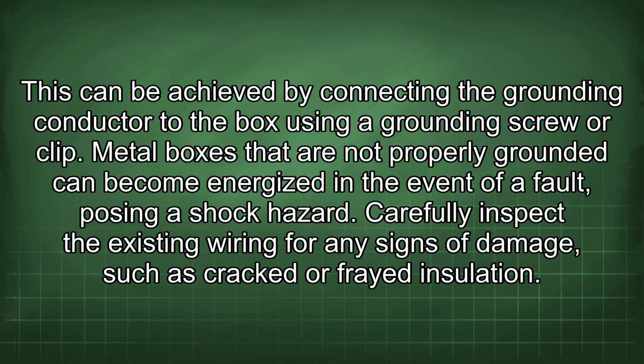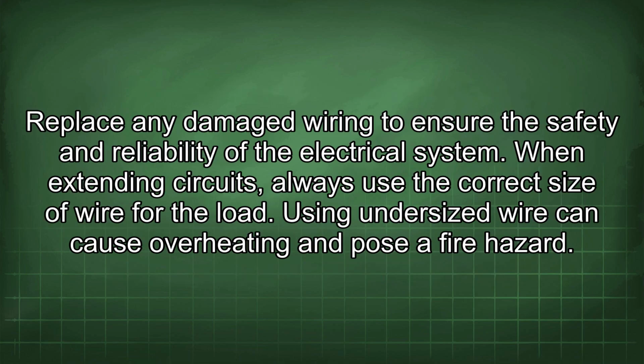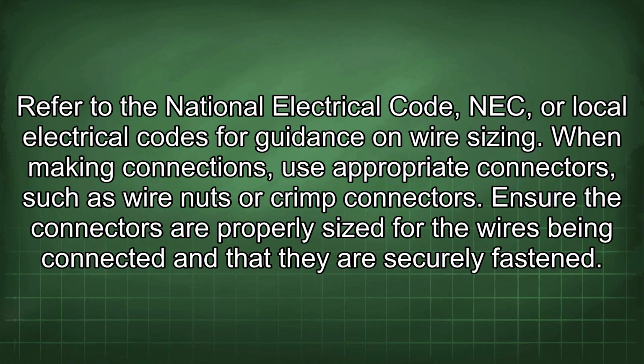Carefully inspect the existing wiring for any signs of damage, such as cracked or frayed insulation. Replace any damaged wiring to ensure the safety and reliability of the electrical system. When extending circuits, always use the correct size of wire for the load. Using undersized wire can cause overheating and pose a fire hazard. Refer to the National Electrical Code, NEC, or local electrical codes for guidance on wire sizing.